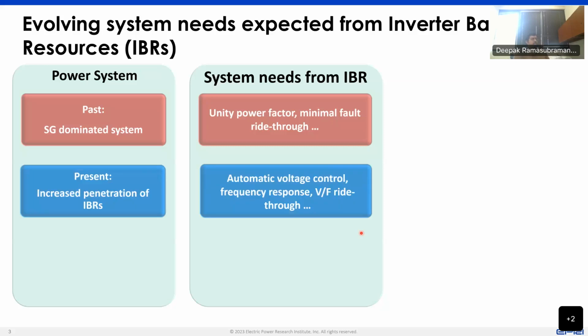We're in a present situation now where there is an increased percentage of inverter-based resources, and that has resulted in FERC orders, IEEE standards, and other associated grid codes. There is now capability required from inverter-based resources to provide services such as automatic voltage control, frequency response, and ride-through behavior. Now, note that this is capability, which doesn't necessarily mean that it is always going to be utilized. As long as the capability is there, the delivery of that service itself depends on other conditions, and some of them could be market conditions.